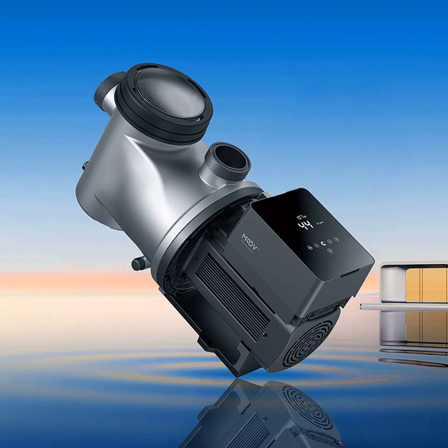So that motor, being a PMSM, is actually going to run much cooler than any other product out there. It creates much less friction because we're controlled by a vector control that's happening in the drive specifically. And a magnet motor as a whole is, of course, always going to be much more silent because of that less friction happening, and the fact that it's going to run a bit cooler as well than the other ones. So we're running this pump right now at 1 meter. You can detect 36 decibels. Often at shows, as we've seen, clients pop in, they look at the product, they want to turn it on, and then they realize that the product is already on. It is that much more silent than any other product that is out there right now.